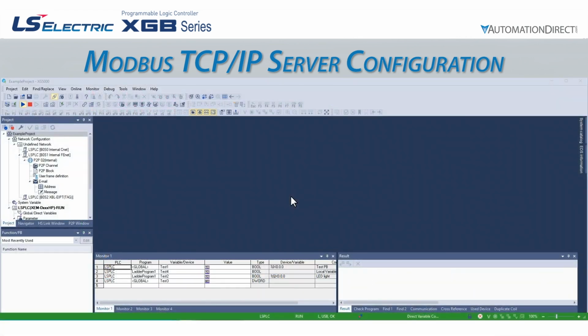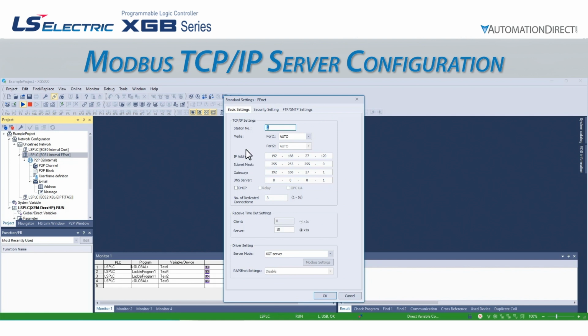Let's set up the XGB PLC as a Modbus server. The first step is to set the TCP IP settings. To do this, we will go to the project window on the left side of the screen and double-click on Internal FENet. This will open the Standard Settings FENet pop-up window. Here we can set our IP address, subnet mask, gateway, and DNS server if needed.